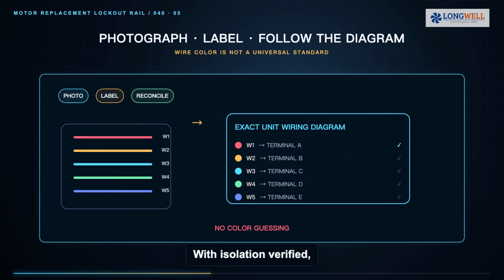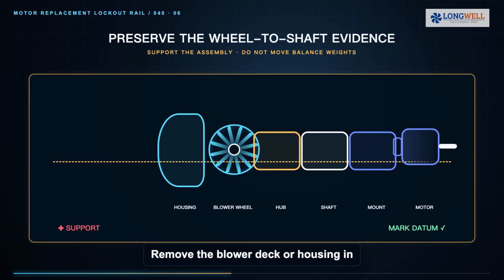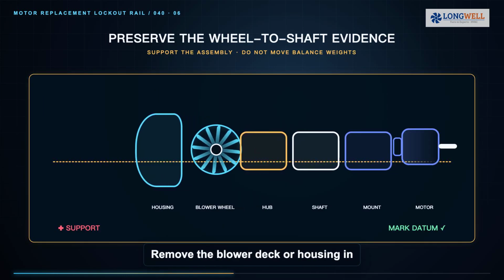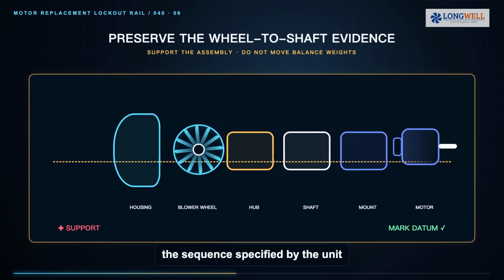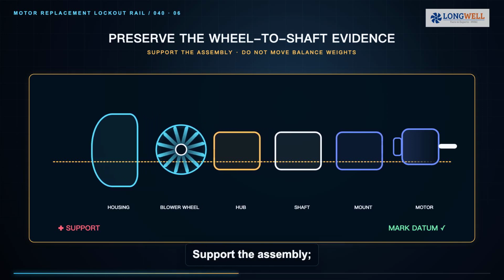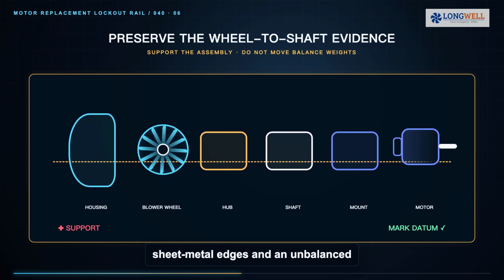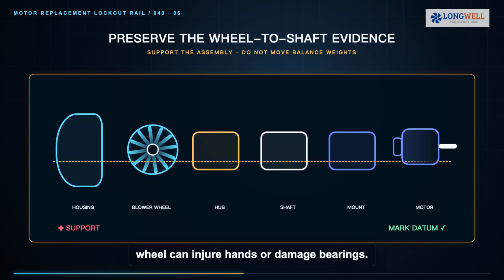With isolation verified, photograph and label every conductor before disconnecting it. Protect loose terminals from damage. Reconcile every label against the exact unit wiring diagram and the replacement motor instructions. Wire color alone is never proof of terminal function. Remove the blower deck or housing in the sequence specified by the unit manufacturer. Support the assembly. Sheet metal edges and an unbalanced wheel can injure hands or damage bearings.